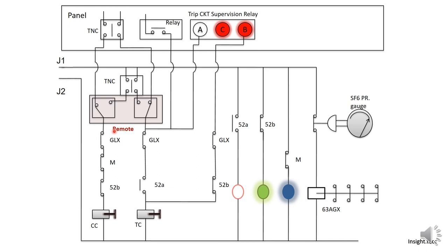Now let us understand another important part of the breaker: the local and remote switch. When the switch is connected to local mode, it gets connected to the TNC switch inside the circuit breaker and it gets operated locally from that TNC switch. Also, whenever the local mode is operated, the breaker can always trip in the protection mode as well. When it is connected to remote mode, the switch is connected through the panel TNC switch, so you can operate the circuit breaker remotely from the control room panel.